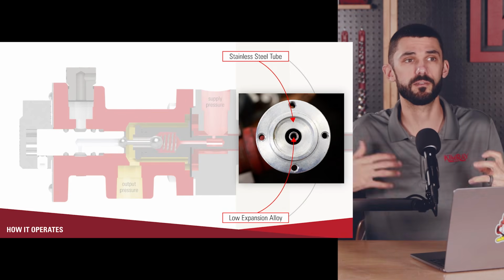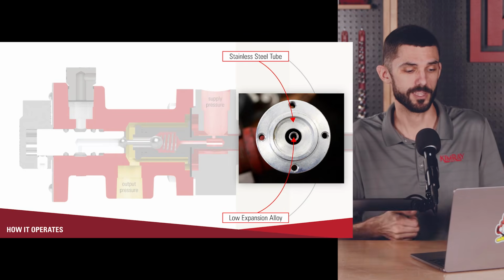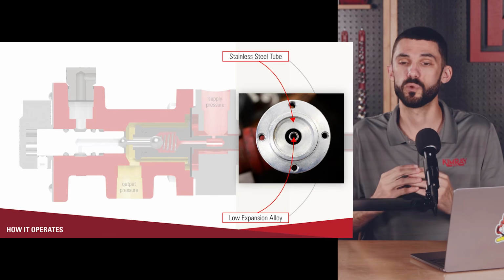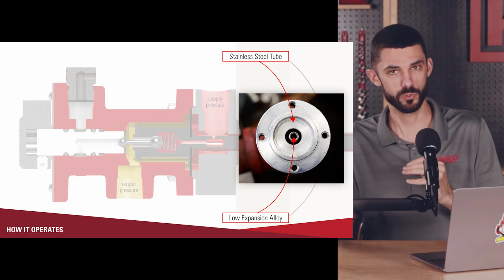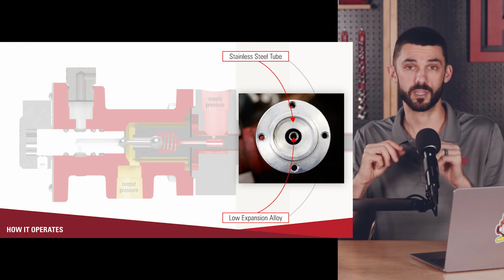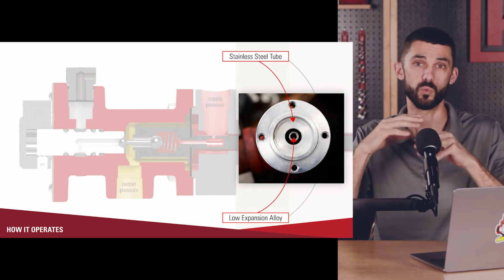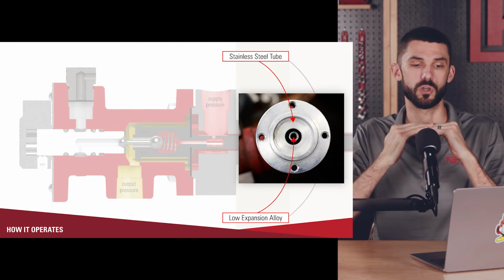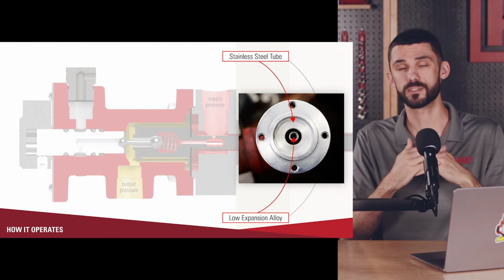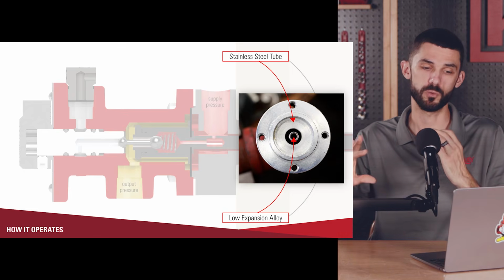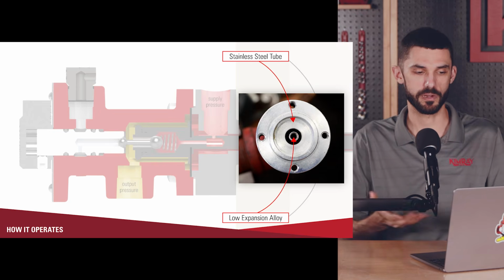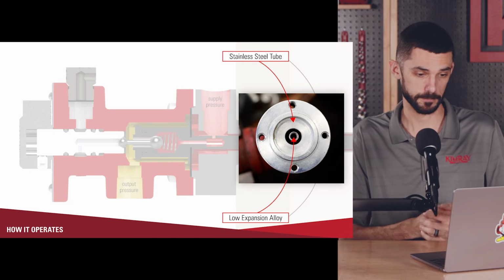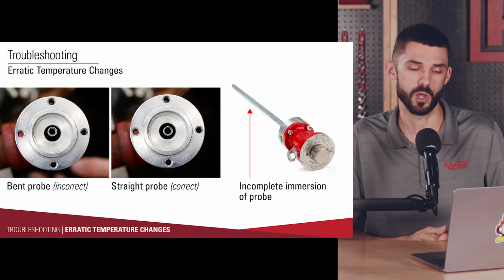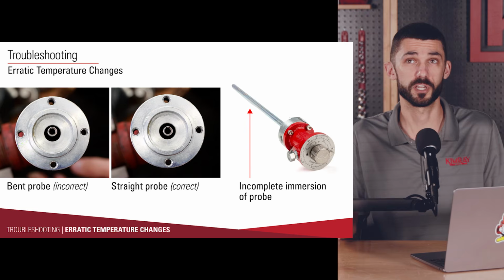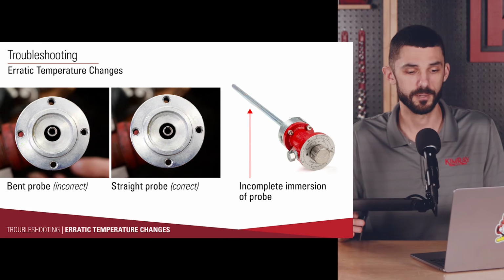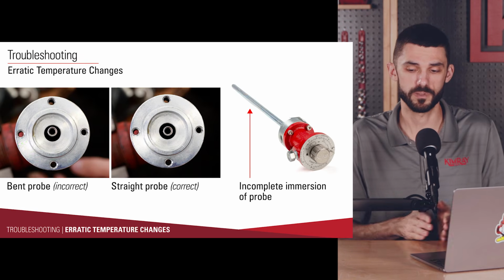It's important when you're installing the T12s, as well as just handling them, that you don't carry it by the probe. We want that to remain straight and true. If it gets bent, that can cause the low expansion alloy to come into contact with the outside of the probe, which could cause issues with it expanding and contracting at different rates. So you want to make sure that the probe is straight, you're not handling it by the probe, and you're carrying it in a way that will protect that. That's one of the troubleshooting tips I would give. If you're experiencing erratic temperature changes, a bent probe would be one of the main causes of that.